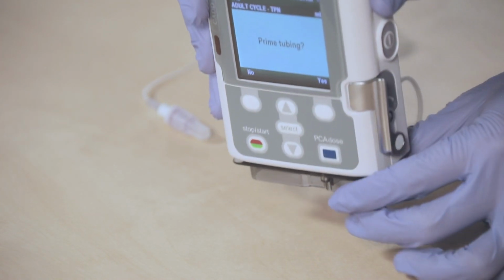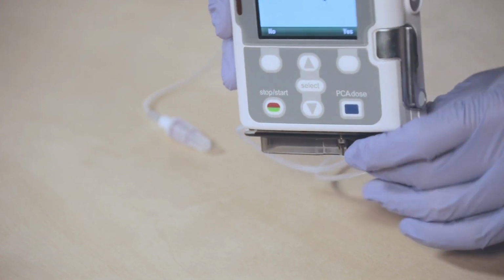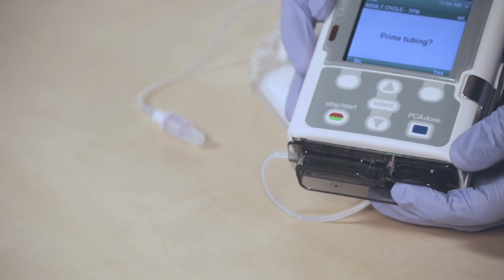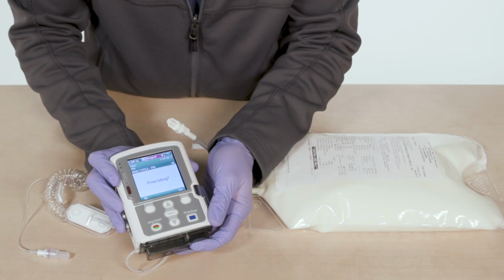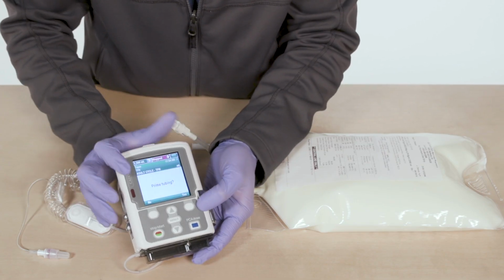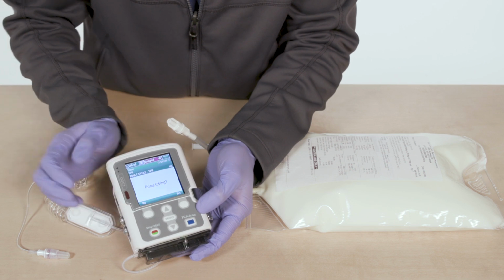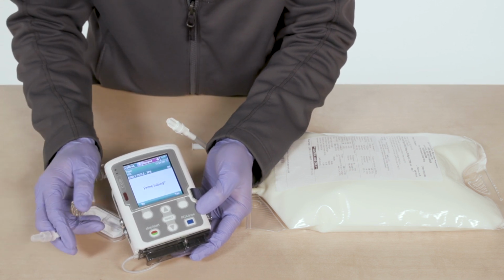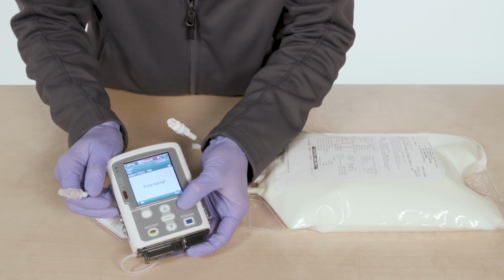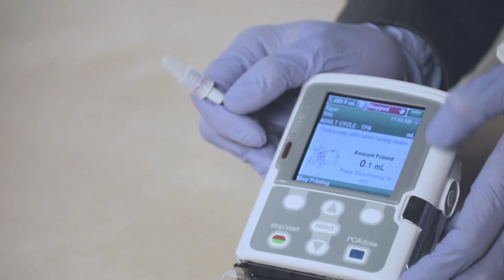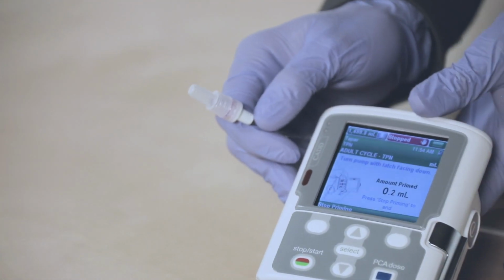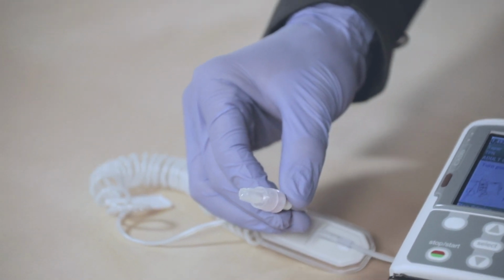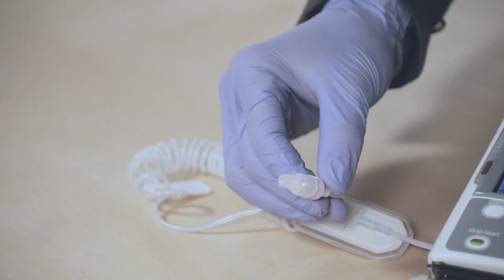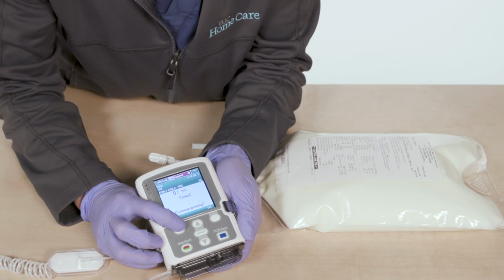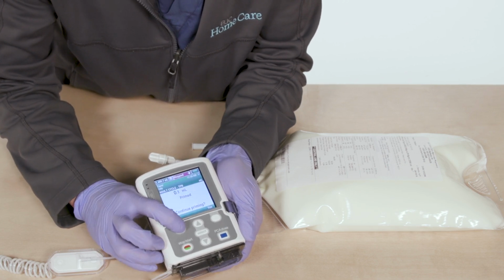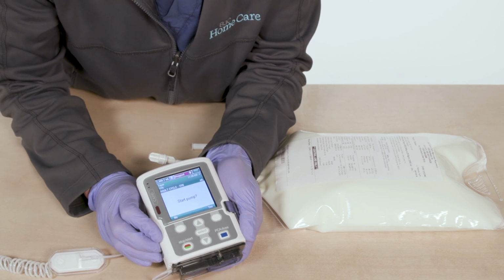This will lock the cassette into place. Check to make sure that the lock mechanism is properly engaged. The screen will then ask if you would like to prime the tubing. Make certain that the tubing is not attached to the patient, then select Yes. The pump will begin priming. Allow the pump to prime until a few drops come out of the end of the tubing. Then select Stop Priming and then select No that you do not want to continue priming.